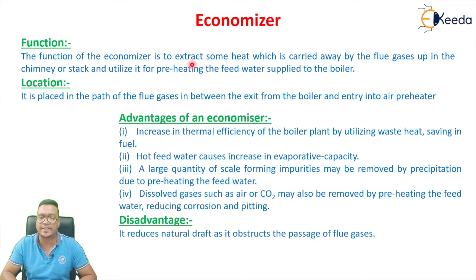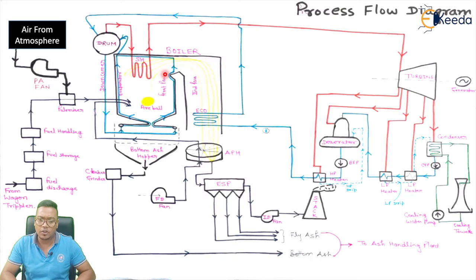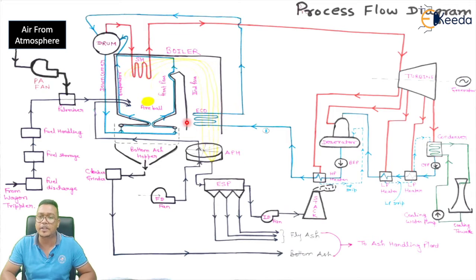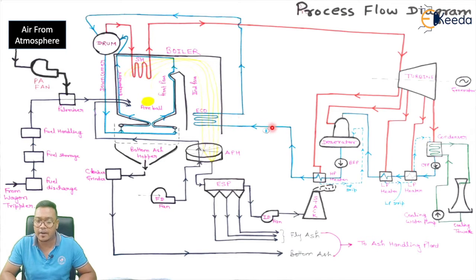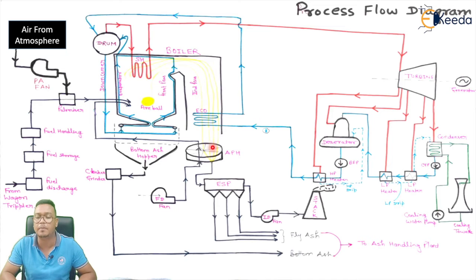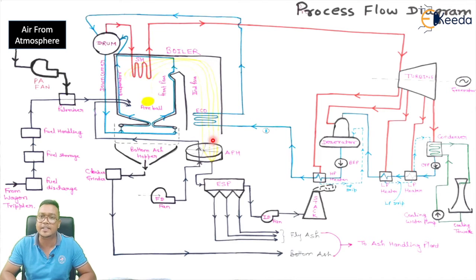The function of the economizer is to extract some heat which is carried away by the flue gas up into the chimney or stack, and utilize it for preheating the feed water supplied to the boiler. If we are not using the economizer for preheating the water, we would have to use extra fuel to preheat the water, and the heat carried by the flue gas would be wasted. So, to recover that waste heat, the feed water is preheated in the economizer. It is placed in the path of flue gas, between the exit from the boiler and entry into the air preheater.